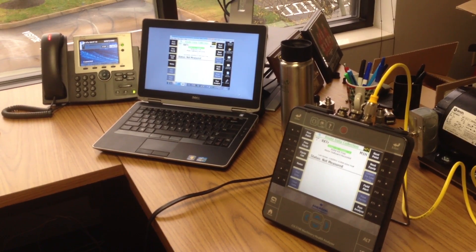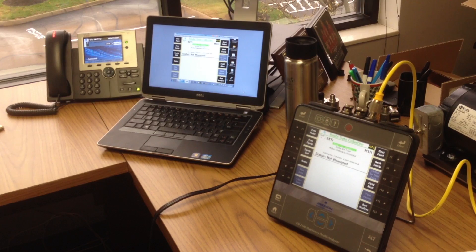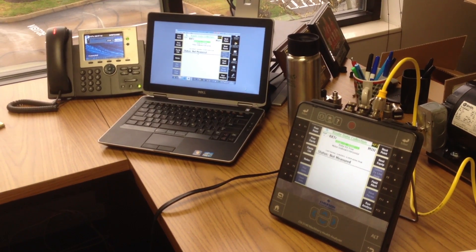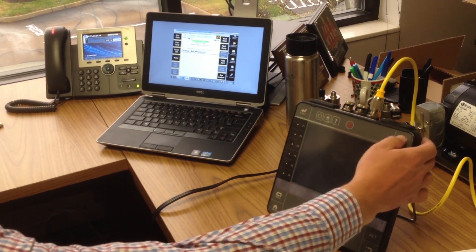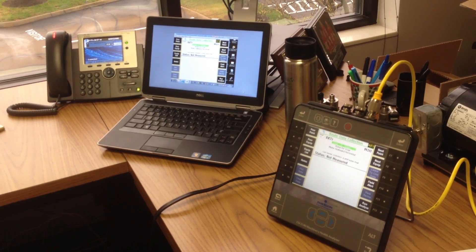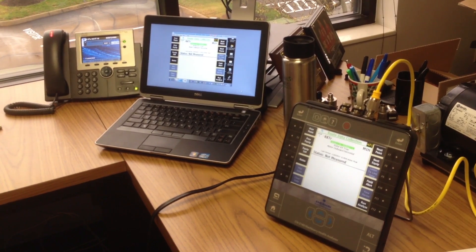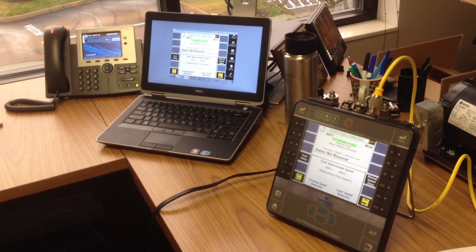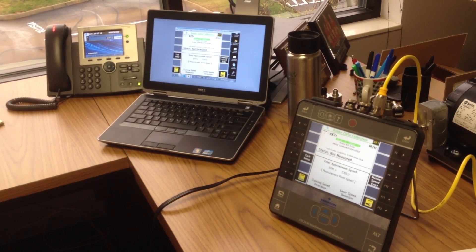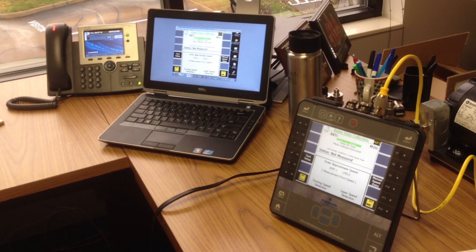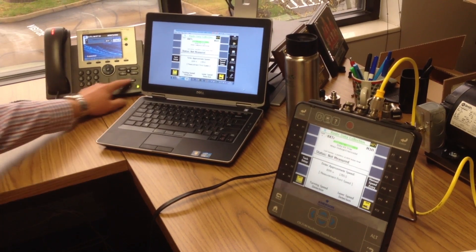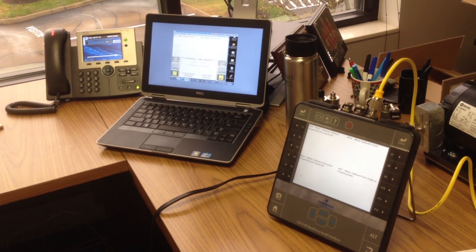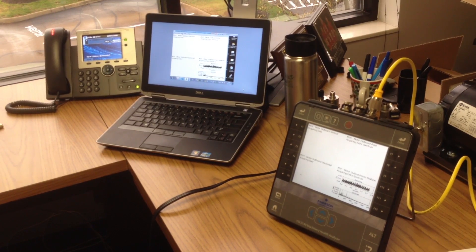We should be able to see the screen change here, if you want to go ahead and maybe collect some data on this route point. I will now initiate the measurement by clicking enter, and I'm clicking enter now. It's pretty fast. He's asking me the speed of the machine, because this machine is variable speed configured. I accept the default speed by pushing enter now, and data collection is starting immediately.